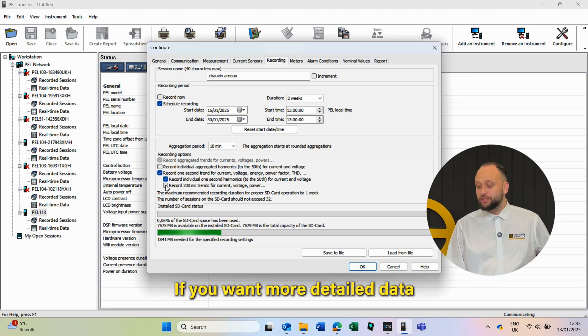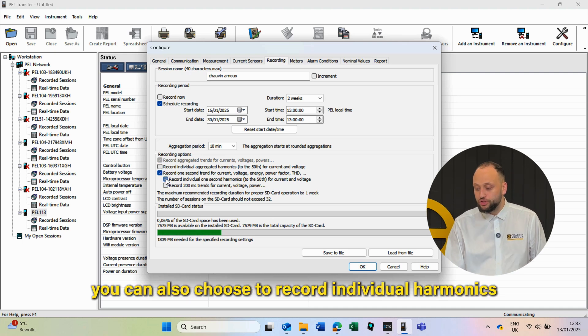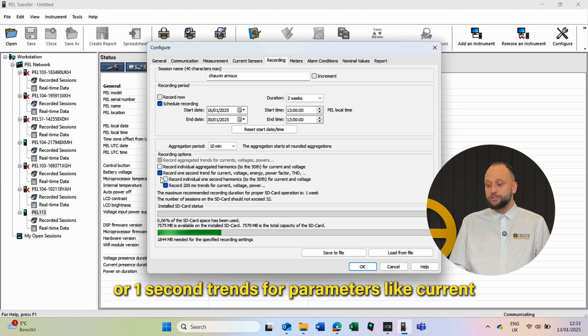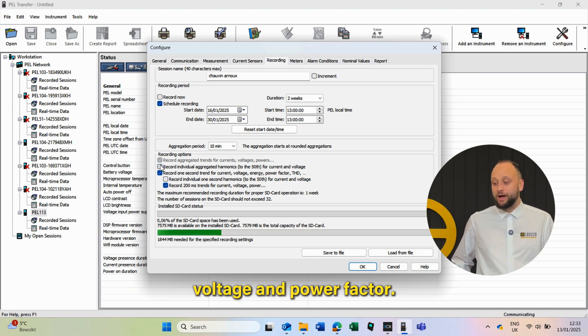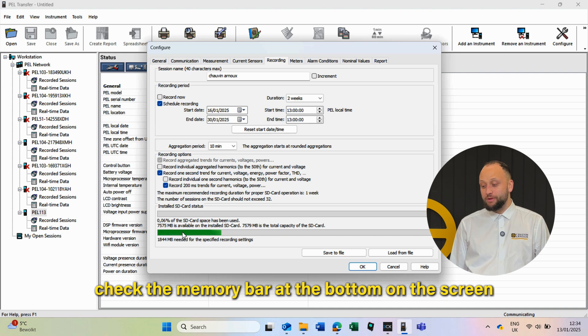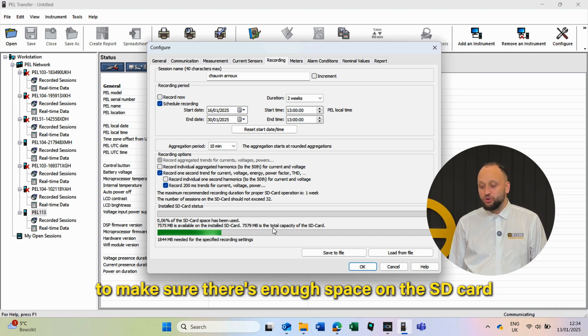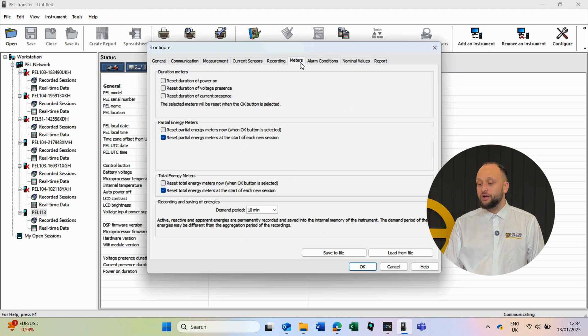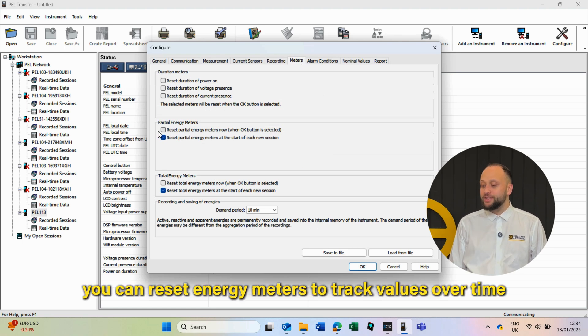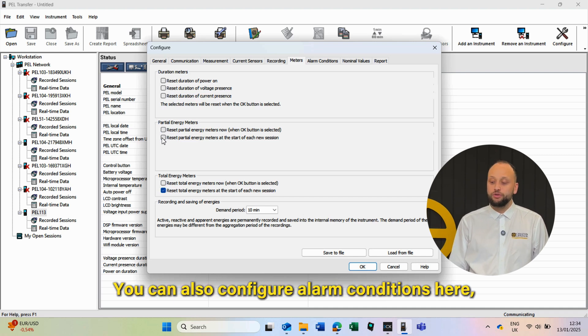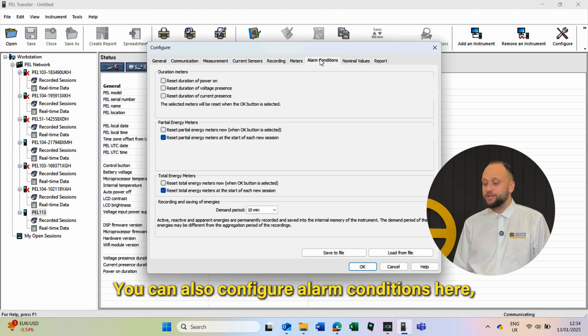If you want more detailed data, you can also choose to record individual harmonics or one-second trends for parameters like current, voltage and power factor. Before starting, check the memory bar at the bottom of the screen to make sure there's enough space on the SD card installed. Under the Meter tab, you can reset energy meters to track values over time and compare them with other equipment.